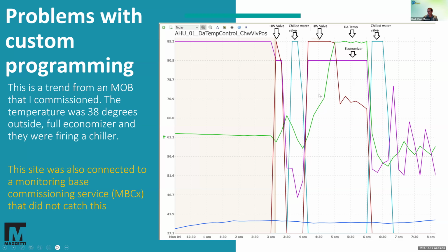These are the things that FDD often isn't going to catch. In this case, it wasn't simultaneously heating and cooling. The FDD doesn't always know if the economizer should be open or not, because there are outside air requirements. So there are some things that honestly need to be commissioned, not to do my own plug. I just wanted to talk a little about that, why we have FDD in the first place, and the importance of good controls commissioning. With that, I'd like to turn it over to Kevin, who's going to talk to us about some energy conservation measures.